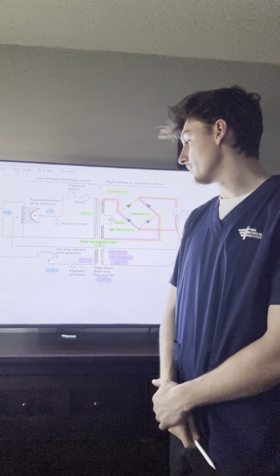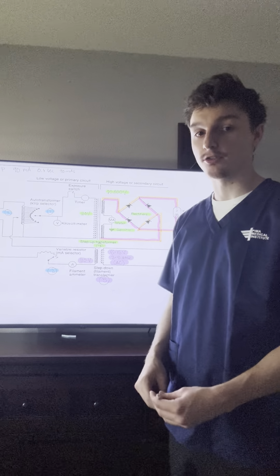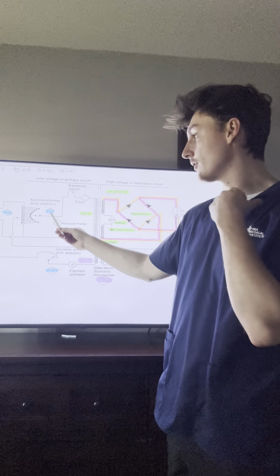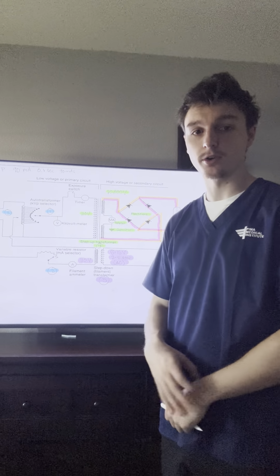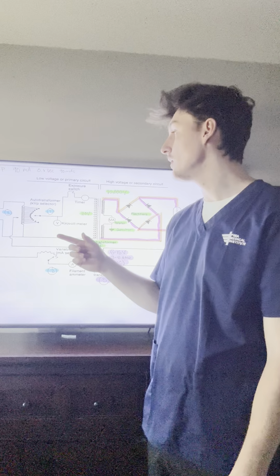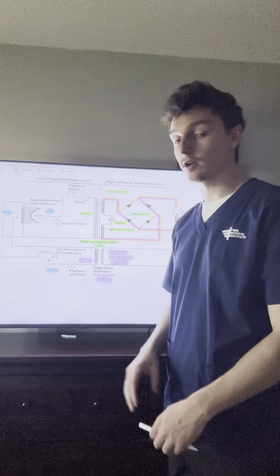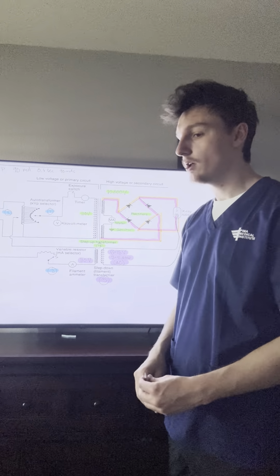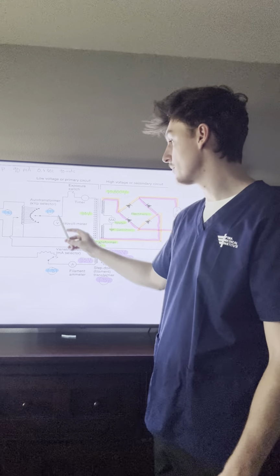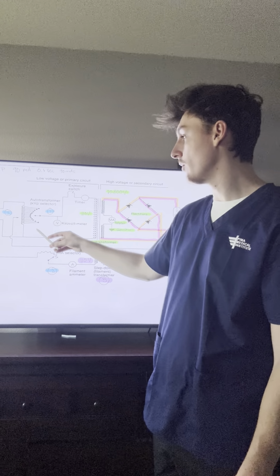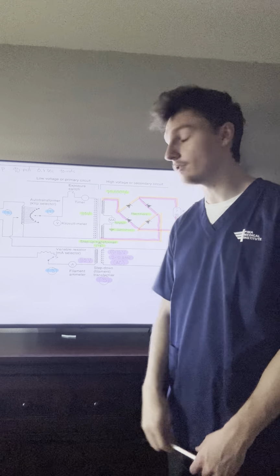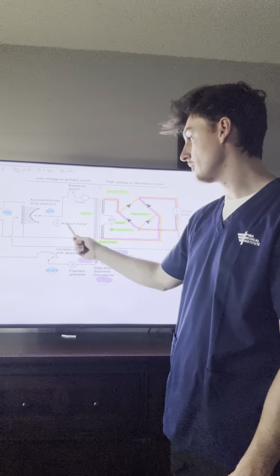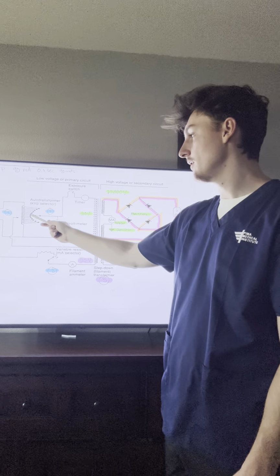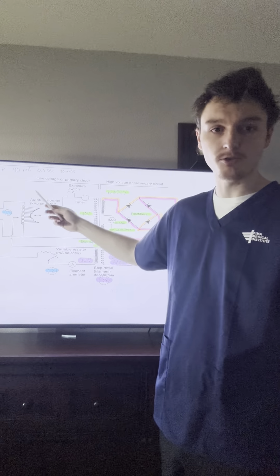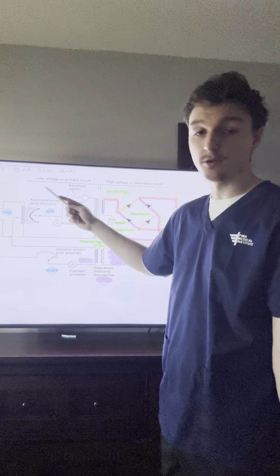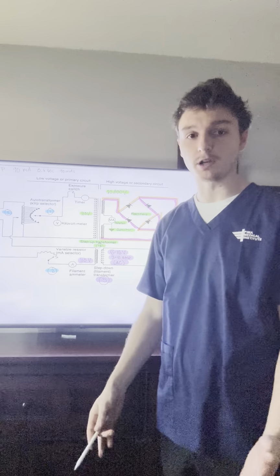The first thing that we're going to talk about, our first point of induction, should I say, is our auto transformer right here, or our kVp selector. We're going to input our technique into the control panel, and then the kVp selector right here will select the appropriate coil for the setting of 70 kVp. It's pointing right here, right by the kilovolt meter. So let's pretend that this is 70 kVp. But let's just say I chose another one like 80. It can move up or move down depending on what the setting is in the appropriate coil.